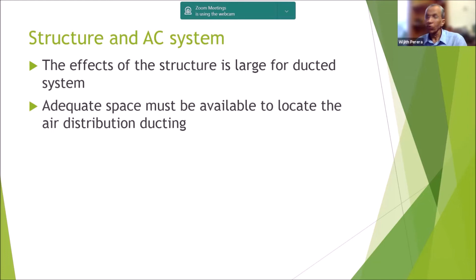That's another misconception we have. I said it deliberately, from the soffit to the floor below, because that is what we are told. But it is not so. Architectural drawings always give us a space between the slab and the soffit, and we look at it and say if it is anything more than 3 meters, and if we have about 3.5 to 4 meters slab to slab, we are very happy. We say, that gives us adequate space to look at our ducting. But there's a catch to it.